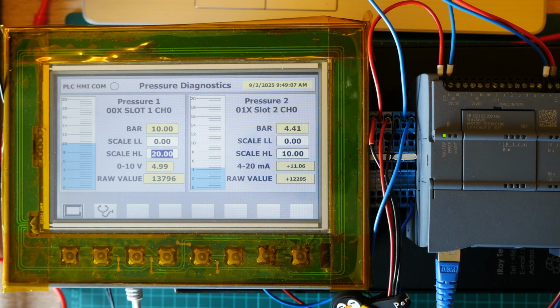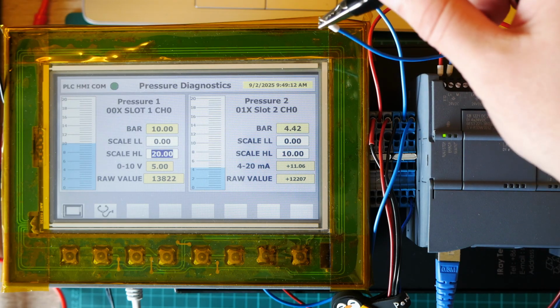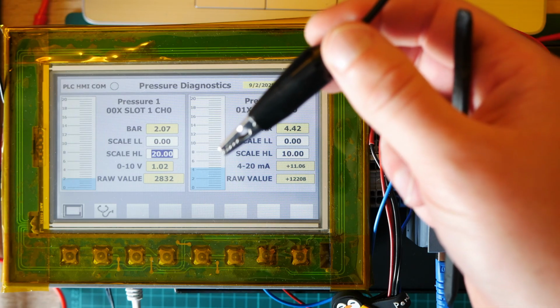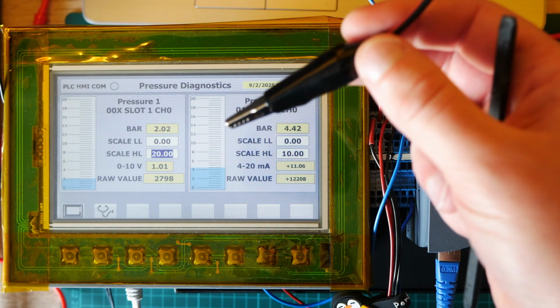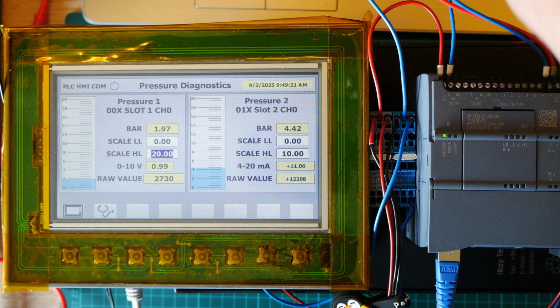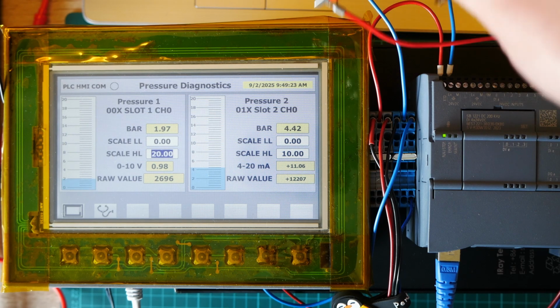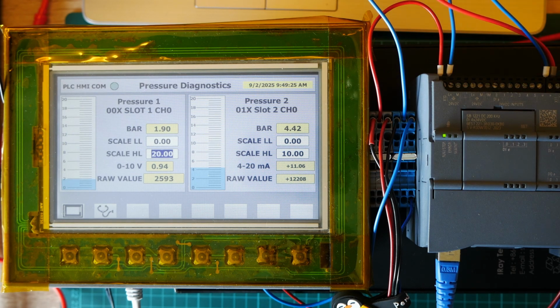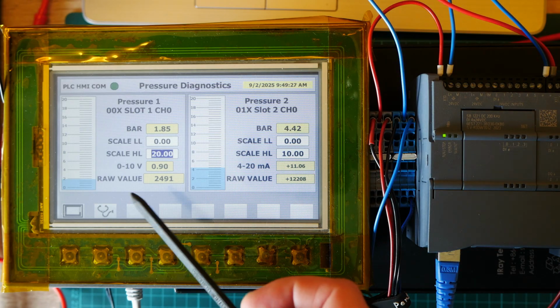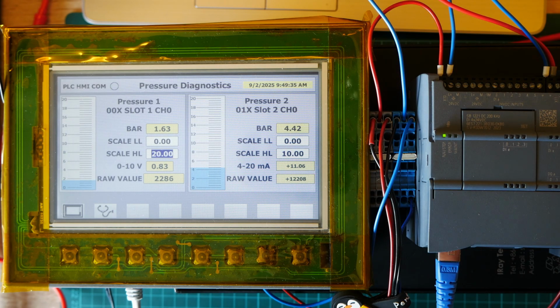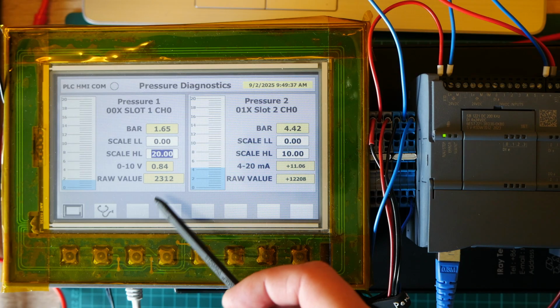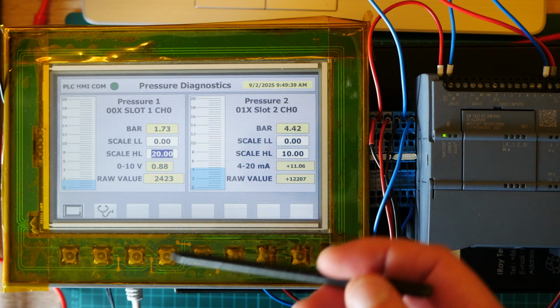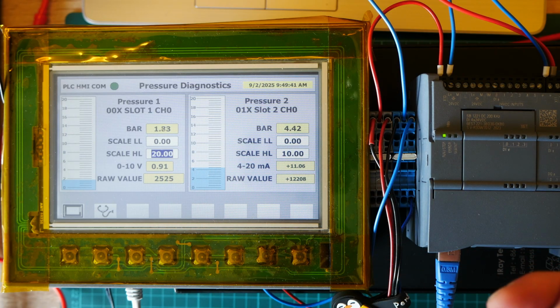Yes. What needs to be remembered: if there is a missing negative contact, right now I disconnected the negative contact, only the positive contact is connected to the analog input, we still have this ghost voltage, and if the electrician sees that, he needs to check the wiring.